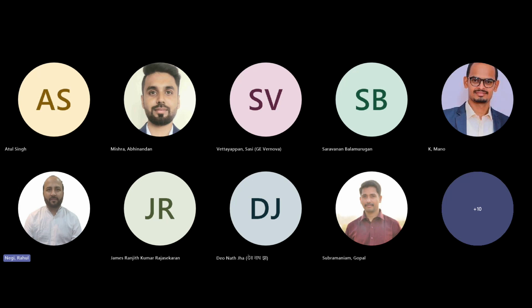Okay, so as of now we do not have any particular environment or setup to get the real-time data and link it with the digital twin technology. It is under progress, or maybe we'll see that in the coming future, right? Currently, we are not manually taking the data and filling it in. This data is coming in through FTP mode, and it is auto-populating in our system. There's no manual intervention there. But if you're talking about real-time integration of SCADA with IT, that is not happening, because I don't think MeitY or CEA allows real-time integration of OT and IT in India. So what is happening in Power Grid is that the data is run in batch mode in the OT system. Some processing is already happening in the OT system to derive relevant values, and then every 24 hours this data comes from OT to the IT system in batch mode.